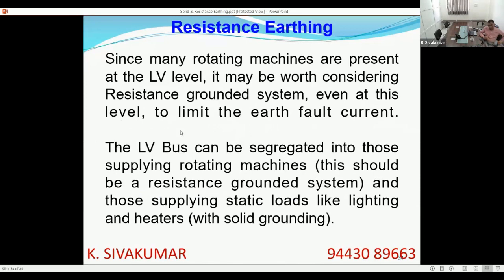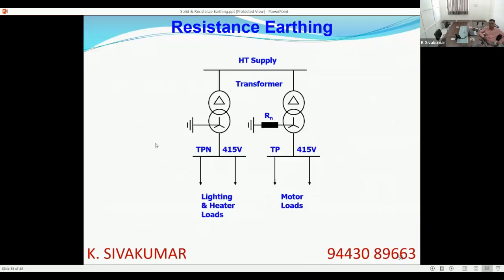Since many rotating machines are present at the low voltage level, it may be worth considering resistance grounded system even at this level to limit the earth fault current. A very simple solution would be bus segregation. The low voltage bus can be segregated into those supplying rotating machines with the resistance grounded system and those supplying loads that are handled by common non-electrical people or common public like lighting and heaters. That must be solidly grounded. Something like this. You put your two transformers. One will be solidly earthed, which will be connected to lighting and heater load. One will be connected to motor loads with the resistance grounding. This way you can follow the rules and you can protect your rotating machines also.